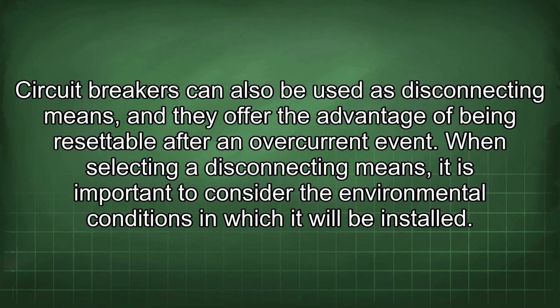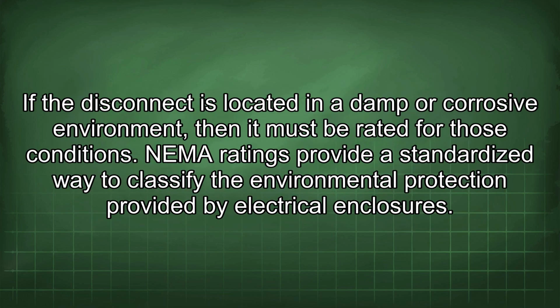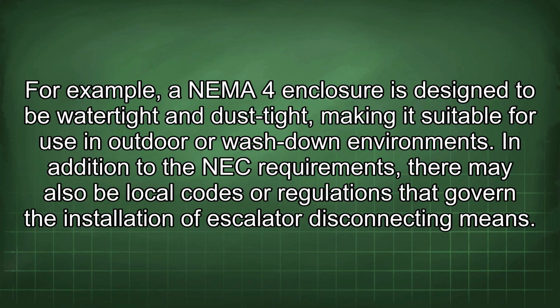When selecting a disconnecting means, it is important to consider the environmental conditions in which it will be installed. If the disconnect is located in a damp or corrosive environment, then it must be rated for those conditions. NEMA ratings provide a standardized way to classify the environmental protection provided by electrical enclosures. For example, a NEMA 4 enclosure is designed to be watertight and dust-tight, making it suitable for use in outdoor or washdown environments. In addition to the NEC requirements, there may also be local codes or regulations that govern the installation of escalator disconnecting means.